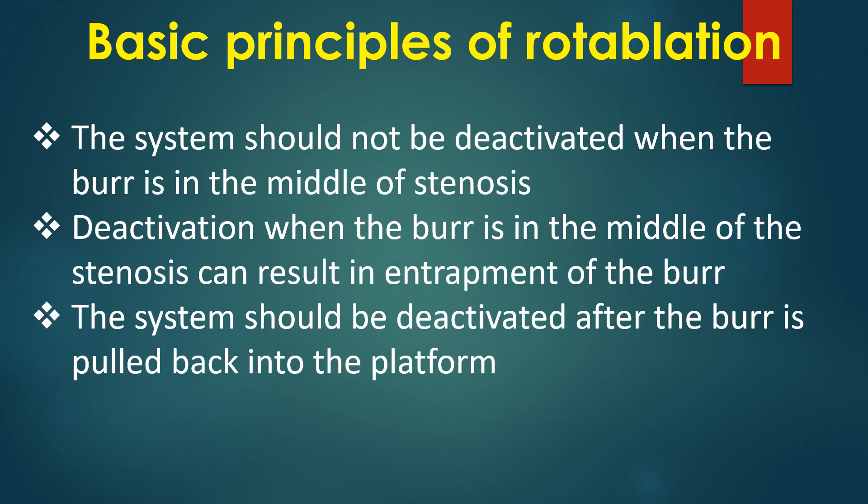The system should not be deactivated when the bur is in the middle of the stenosis. Deactivation in that position can result in entrapment of the bur. The system should only be deactivated after the bur is pulled back into the platform.